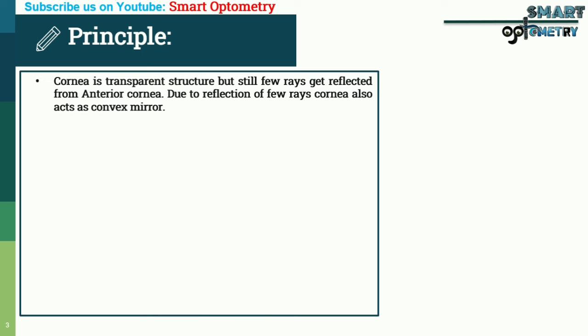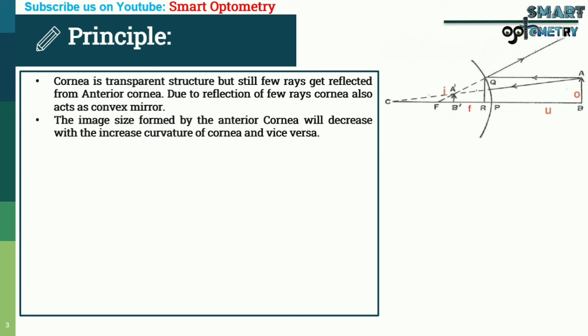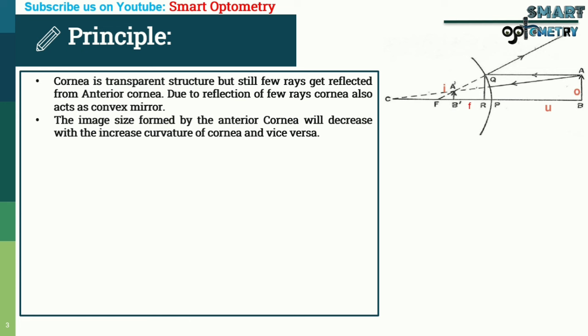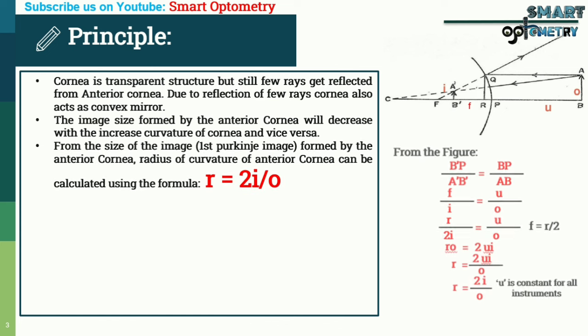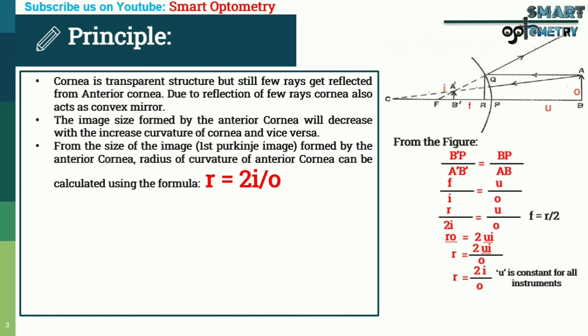The principle of keratometer: the cornea is a transparent structure, but still a few rays get reflected from the anterior cornea. Due to this reflection, the cornea also acts as a convex mirror. The image size formed by the anterior cornea decreases with increased curvature and vice versa. From the size of the first Purkinje image formed by the anterior cornea, the radius of curvature can be calculated using the formula R = 2i / O.